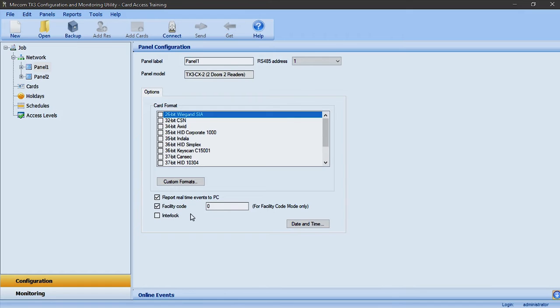Facility code mode allows you to grant access based on the facility code of the credential only; the panel will not look at the card number of the credential to grant access. By enabling interlock, the panel will operate in a way where door B cannot be unlocked until door A is locked and vice versa. This feature is commonly used in jewelry stores.